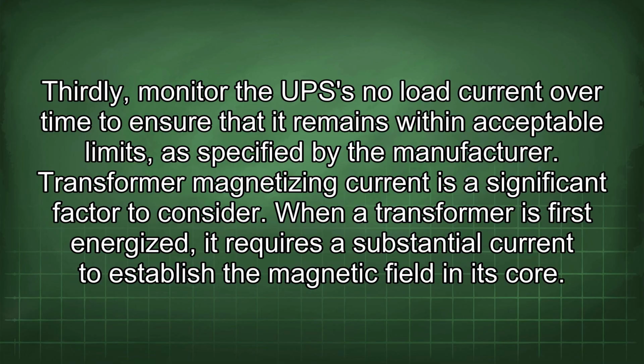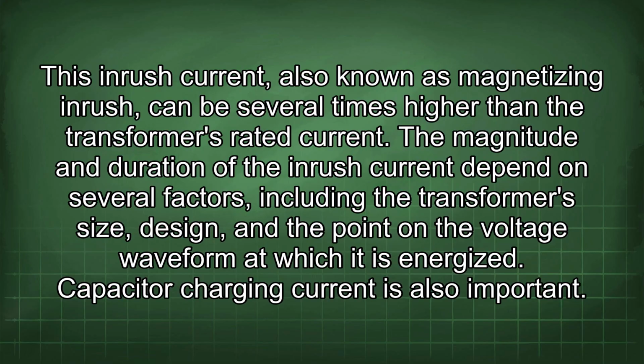When a transformer is first energized, it requires a substantial current to establish the magnetic field in its core. This inrush current, also known as magnetizing inrush, can be several times higher than the transformer's rated current. The magnitude and duration of the inrush current depend on several factors, including the transformer's size, design, and the point on the voltage waveform at which it is energized. Capacitor charging current is also important.